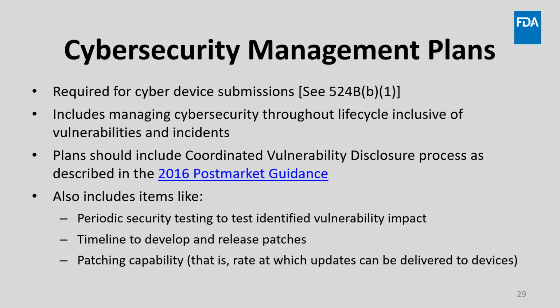These plans should include coordinated vulnerability disclosure processes, such as those described in the 2016 Postmarket Guidance, and also include items like periodic security testing, in order to test identified vulnerability impact and look for new potential risks, the timeline to develop and release patches to the device, as well as the patching capability, or the rate at which updates can be delivered to devices if there's a need identified.